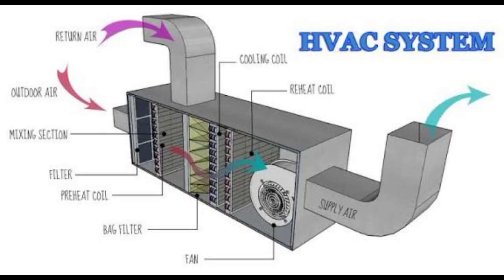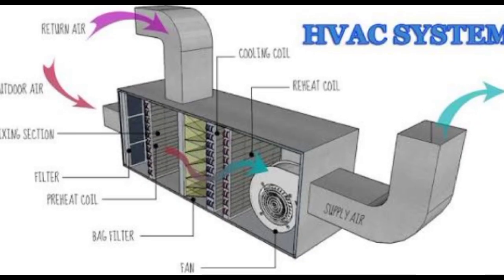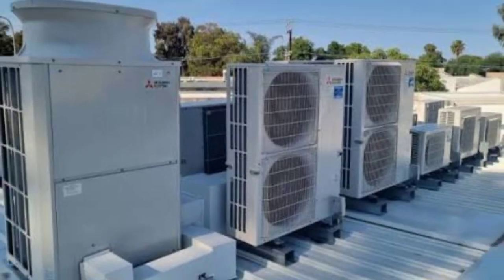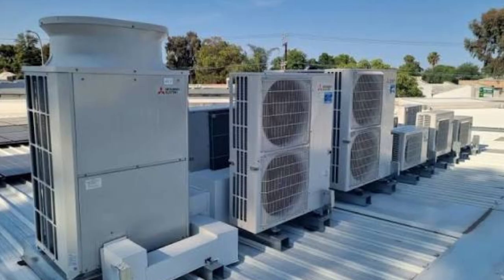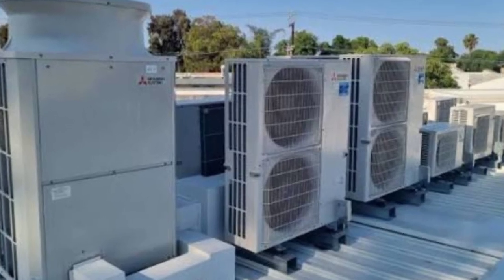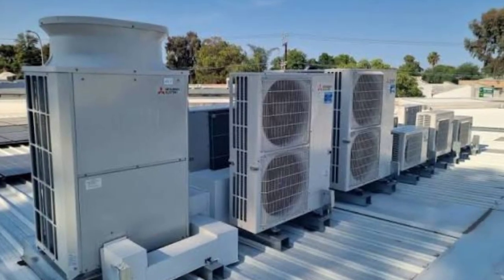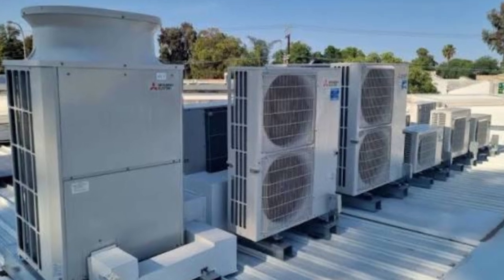They call it rule of thumb sizing, and they almost always round up. Why? Because an oversized system still cools the house. The homeowner feels cold air coming out of the vents, so they think it's working great. But what's actually happening is destroying the system from the inside.